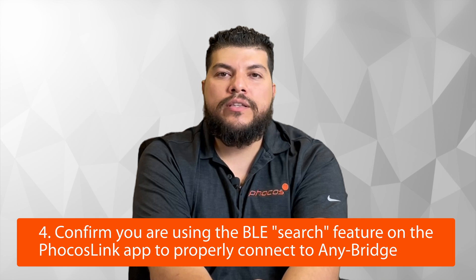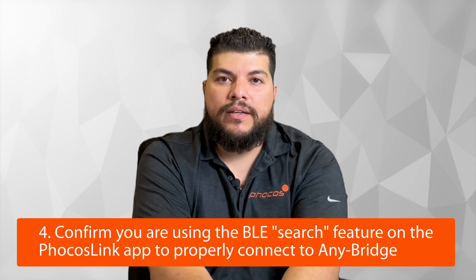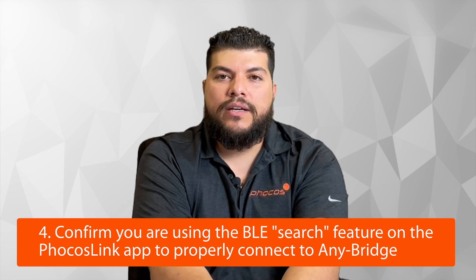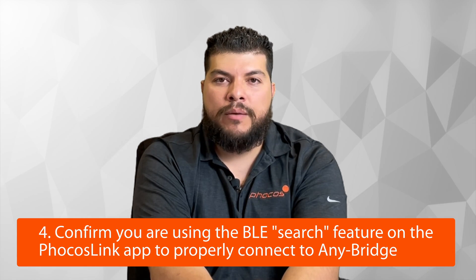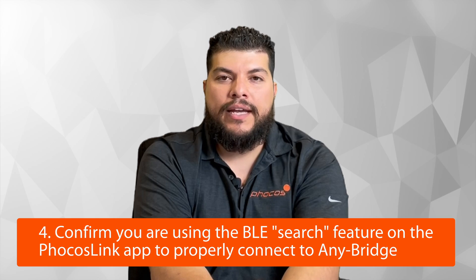Another common issue is a user trying to connect to the Anybridge using the Bluetooth settings on their phone, rather than the Bluetooth feature through the PhocosLink app. You cannot pair to the Anybridge or the inverter using your phone's native Bluetooth settings the way you would connect to headphones. You need to download the PhocosLink app, use the search feature, find the Anybridge through the app, and the app uses your phone's Bluetooth to detect the Anybridge. Doing it directly through your phone's settings will result in errors and will not allow you to pair the Anybridge to your inverter.